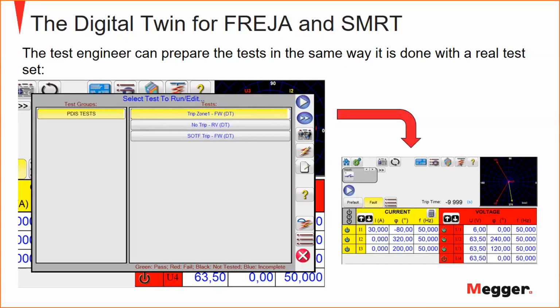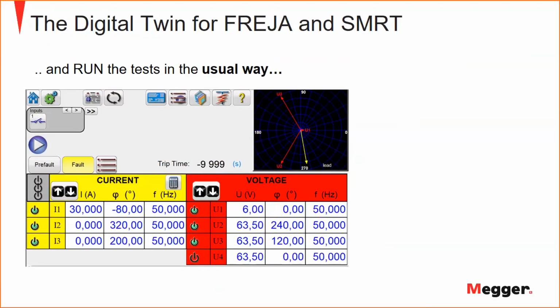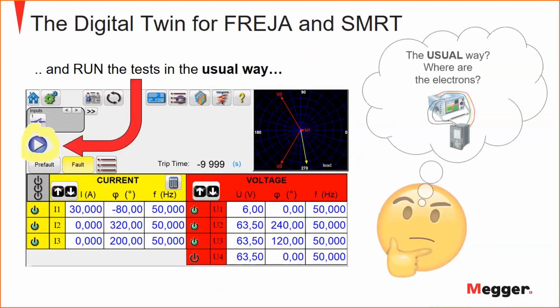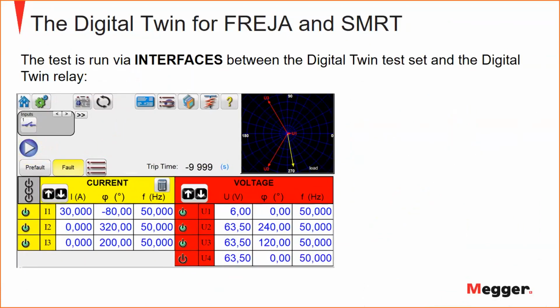What happens when I run them? You press the button, run. And I would like you to understand, this is, for example, a phase to ground fault in forward direction. I say, what would happen? Where are the electrons? Where are these currents? Where are these amperes? Where are these volts? At the moment, the test is run via an interface between the digital twin test set and the digital twin relay. So we have to listen to the digital twin relay. That's why we had to partner with Siemens.